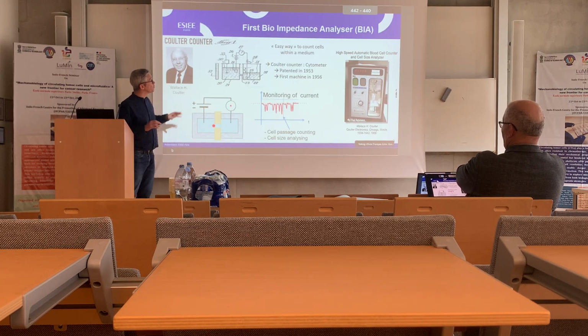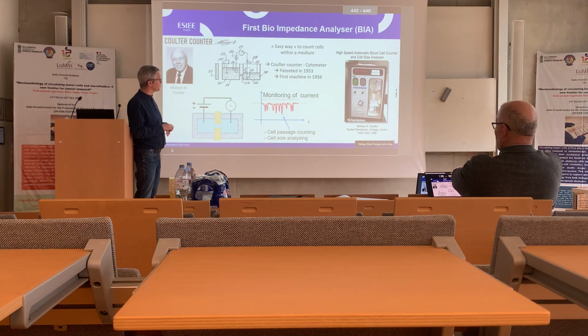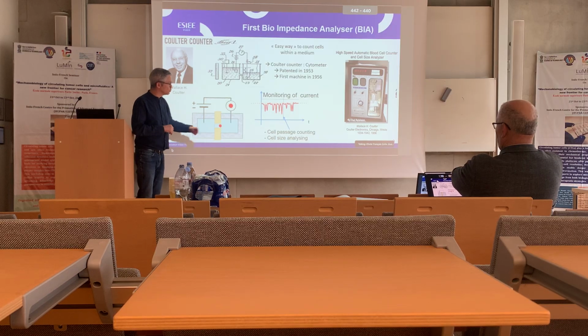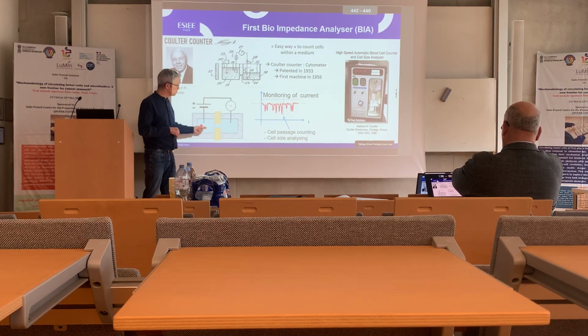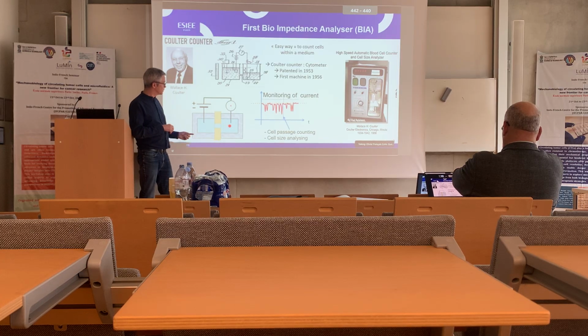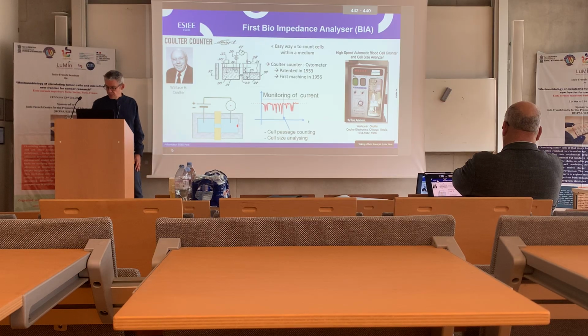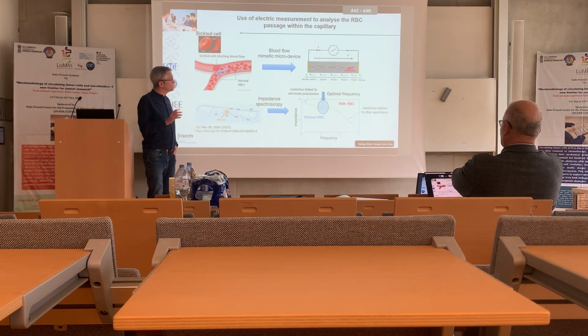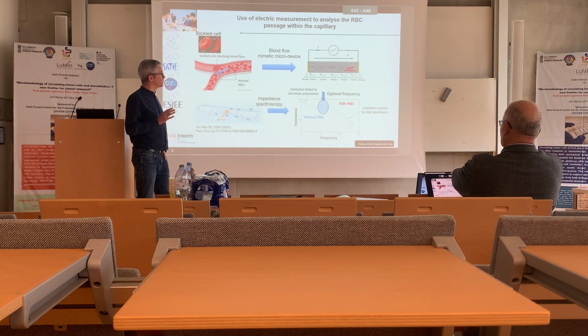So the principle is very well known. It's a bioimpedance analyzer. It comes from the 60s, with Professor Coulter, who created the Coulter counter, which is a way to count cells across a small hole by monitoring the drop of the current when the cell passes through the hole. You have two electrodes on either side of the hole. You control the current. If one cell passes through the hole, you have a decrease of the current, so you can do some analysis of that.